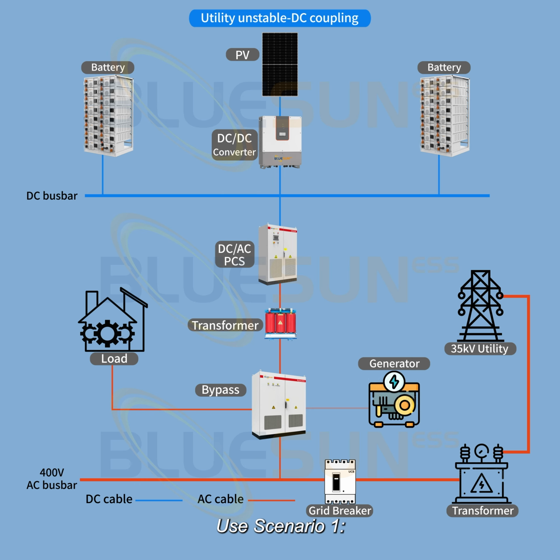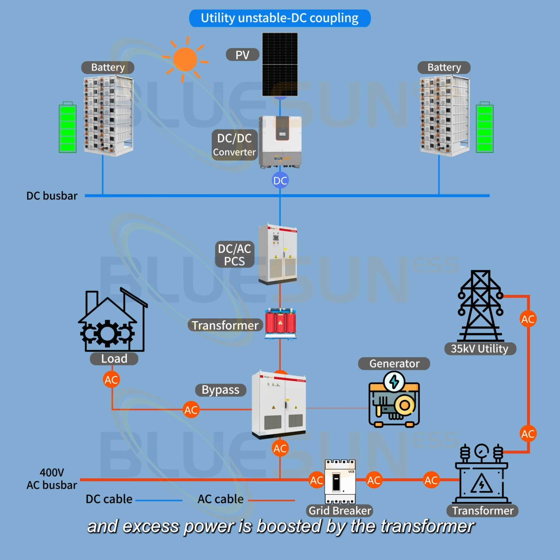Use Scenario 1. Grid-connected operation. During the day, the PV panels convert solar energy into DC power, which is stabilized by the DC converter and fed into the PCS, where it is converted to AC power for the load. Excess power is used to charge the battery. When the battery is fully charged, charging stops, and excess power is boosted by the transformer and fed into the grid.